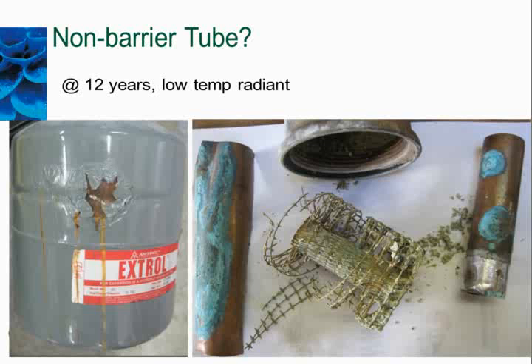I'm not sure exactly what that's made out of, but that's not something you want washing through your tubing in your system, because it's going to do exactly what the picture before showed with the ferrous components. It's going to start plugging up your tubing, zone valves, and other components. And even with all the right steps, if you've got a product in there causing oxygen to get into the system, this is going to be an ongoing problem.